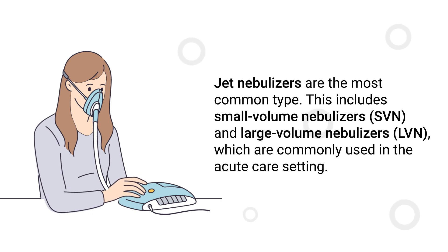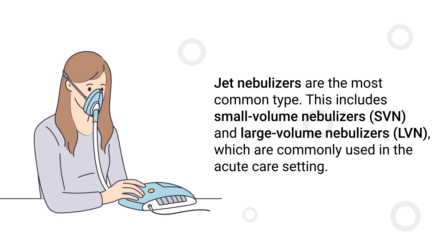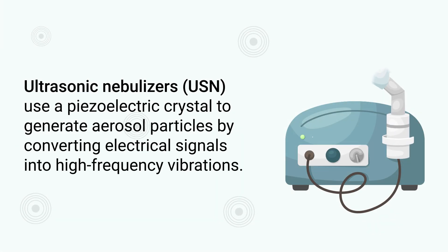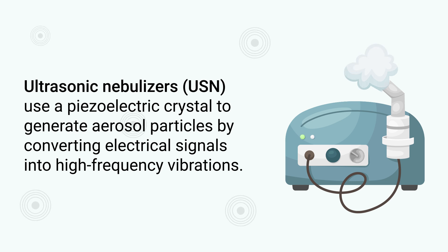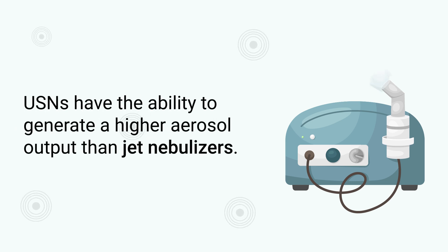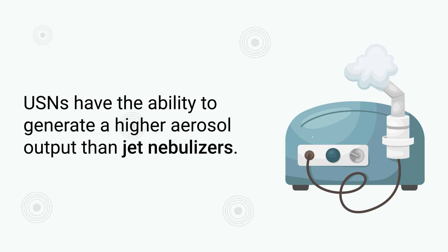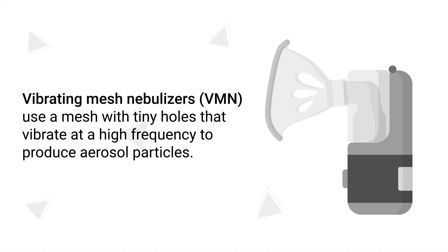Jet nebulizers include small volume and large volume nebulizers, which are commonly used in the acute care setting. Ultrasonic nebulizers use a piezoelectric crystal to generate aerosol particles by converting electrical signals into high frequency vibrations. This type has the ability to generate a higher aerosol output than jet nebulizers.